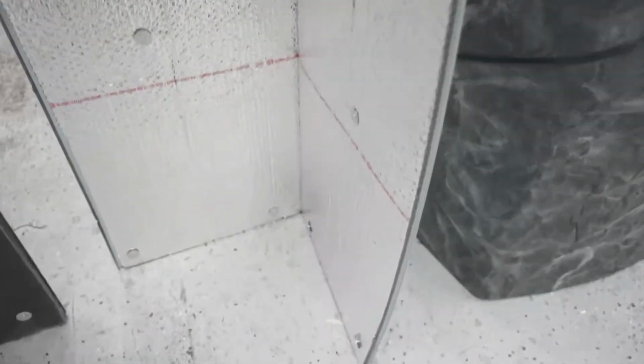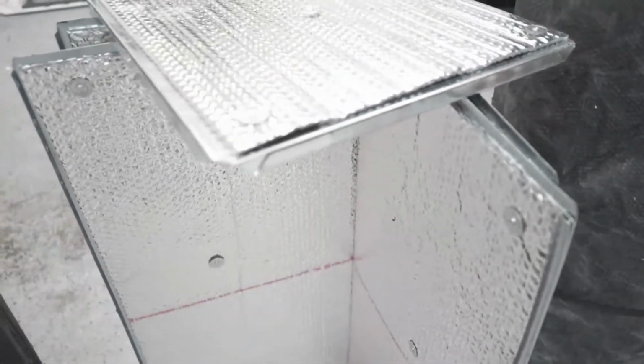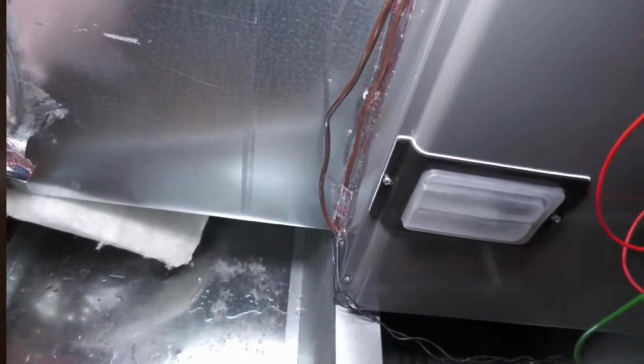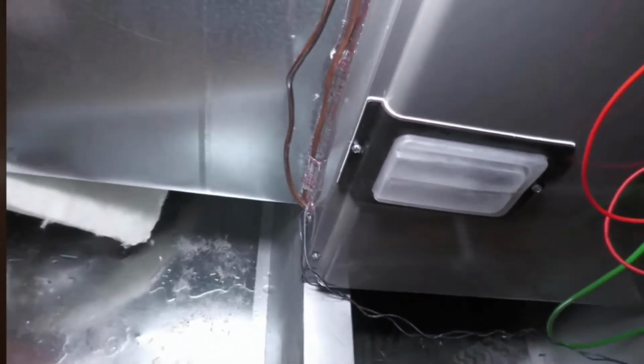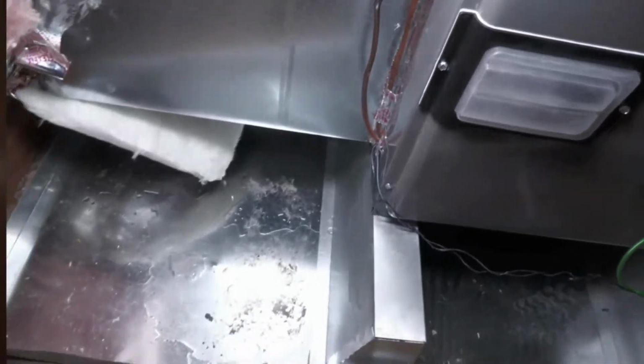My problem with the stuff is it was being used as a liner. I didn't discover this till we were up in an attic and noticed that a plenum was dripping water, and I asked if this was lined, and they said, yeah, it was lined with that astrofoil. Well, the problem there, astrofoil is not approved as a duct liner. So what happened is the side of the metal was getting so cold in the attic, it was hitting the dew point, and moisture was running down. So we ended up having to wrap that whole plenum with FSK. We used 2-inch FSK that eliminated the moisture and it hitting the dew point in the attic, and that solved the problem.